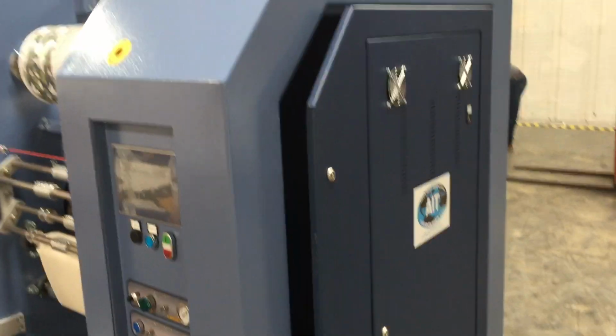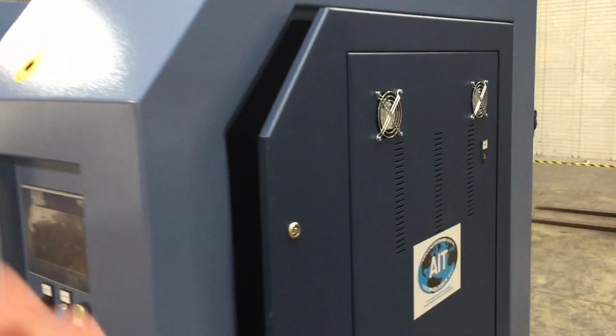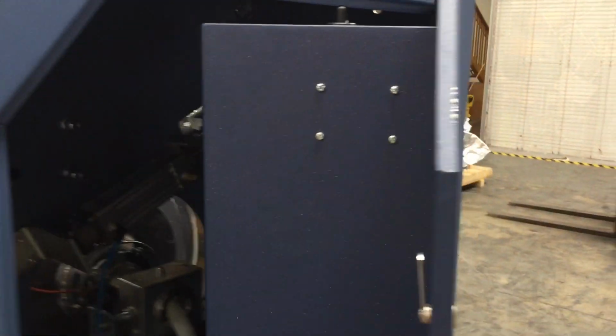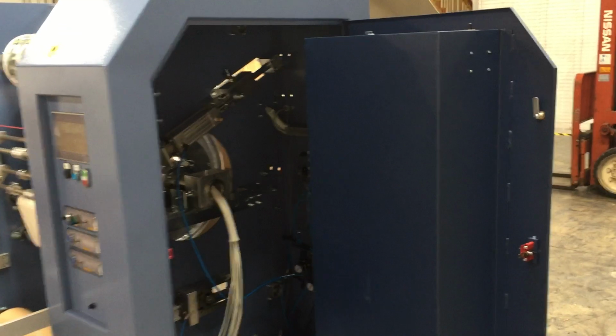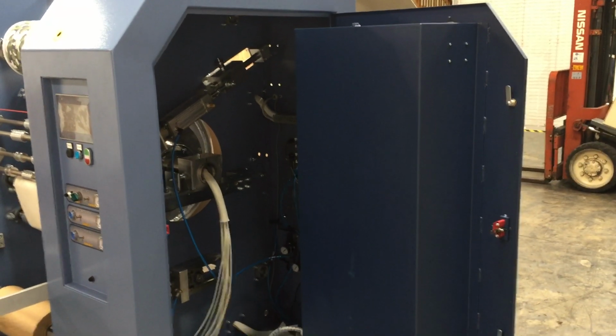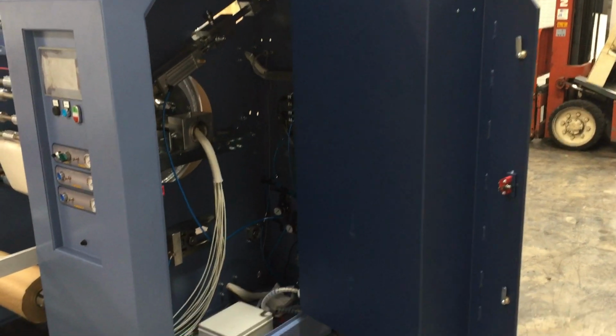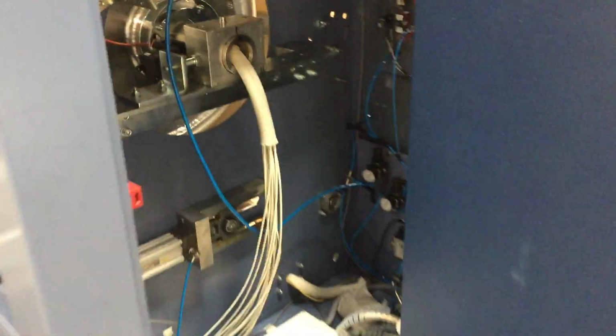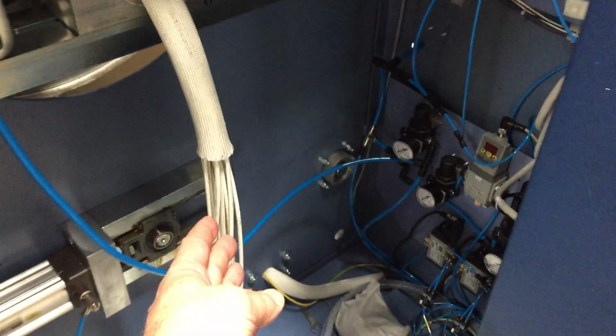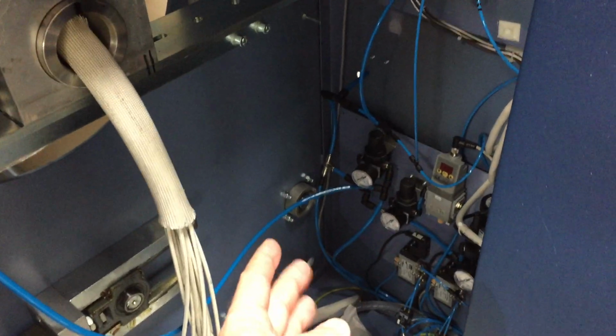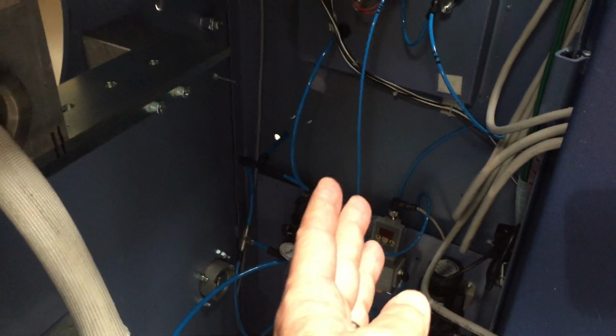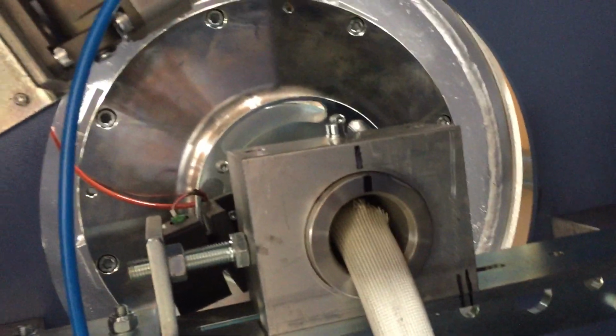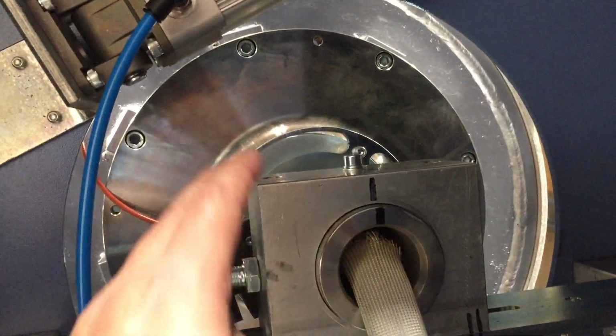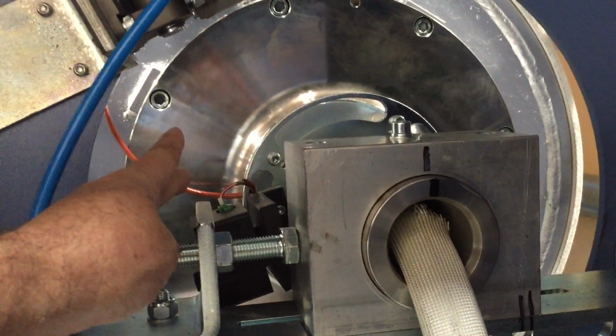Some great features we've added to all our equipment, and of course on the 7616, is we've got kind of a cabinet in a cabinet. Here's the control cabinet side of the machine, and you can see the motors, the heating element leads, etc., the pneumatic tracking system. Here's a side view of that oil heated drum, and you can see the thermocouple wire, the orange one.